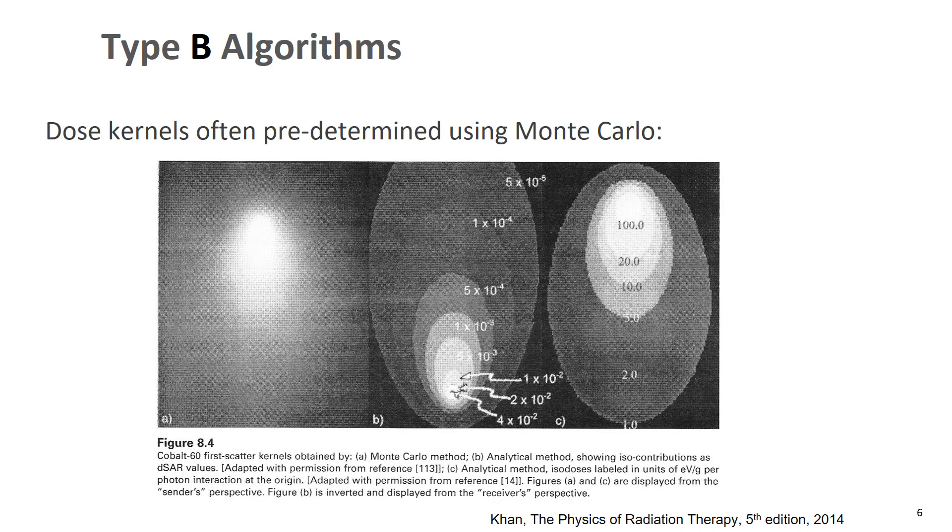So for a dose convolution superposition algorithm, what exactly is the dose kernel? Well, the dose kernel represents the energy spread resulting from interactions at a given point or line. So you can have a kernel for either a line or a point. And the energy spreads because charged particles and scattered photons carry energy away from the site of that primary interaction.